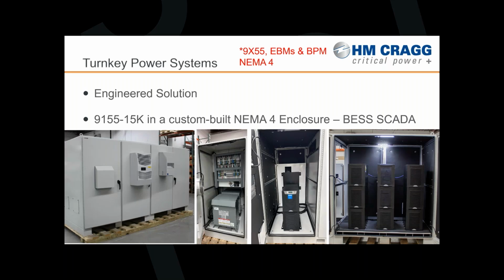What was really unique is this was a BES system, very large scale, built and designed overseas. It was a 230 volt UPS application, line neutral ground, a very unique voltage scheme for North American UPSs. So we provided an input transformer running into our UPS system and back out through another output transformer to provide the native voltage needed at the site.